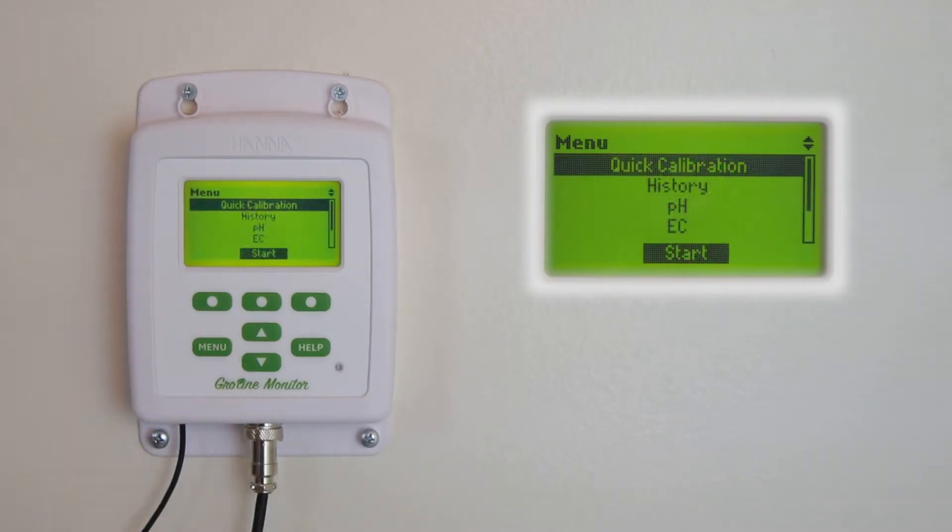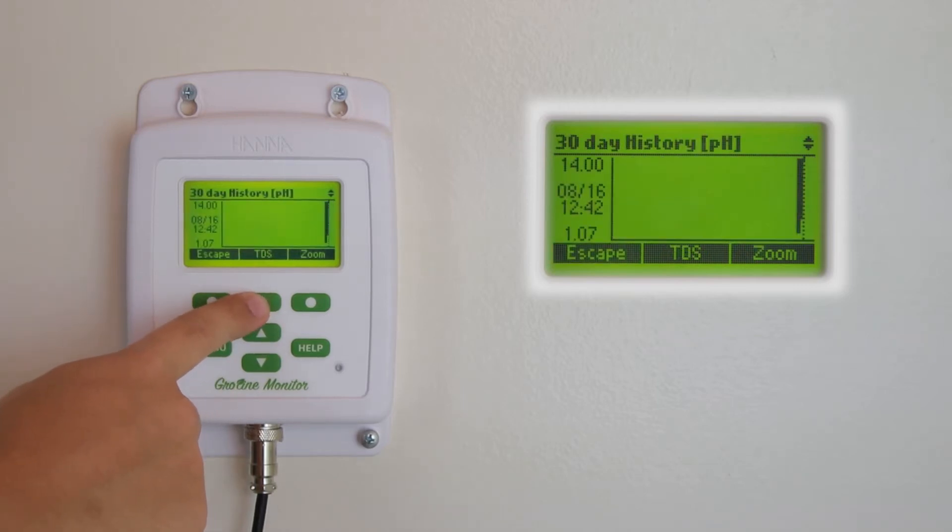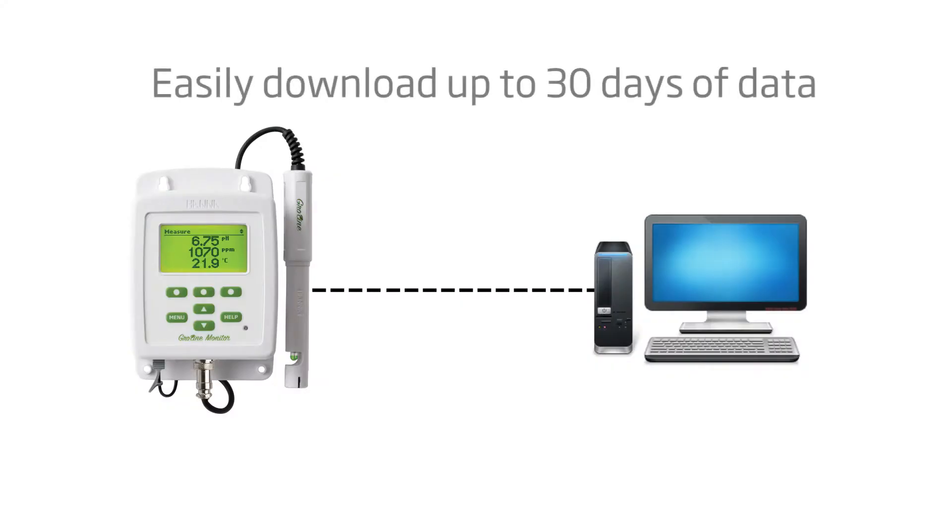By pressing the menu button, you are brought to the main menu screen. Here you will find Quick Calibration, which allows you to use the HANNA QuickCal solution to calibrate both for pH and EC/TDS at once. History gives you 30 days of logging information, which can be backed up and downloaded to a PC or USB drive.